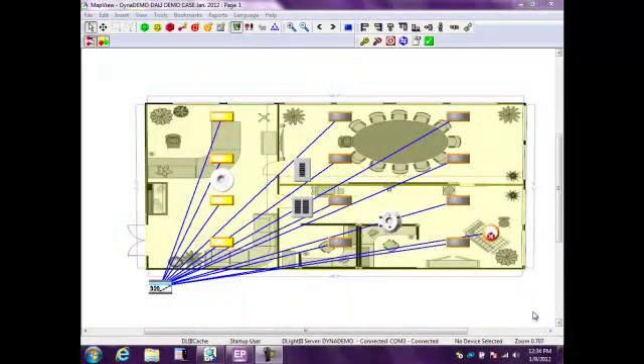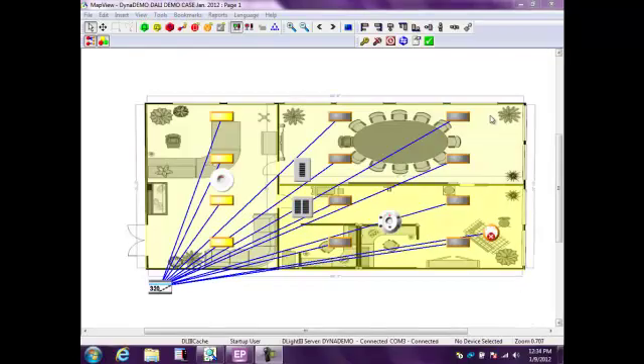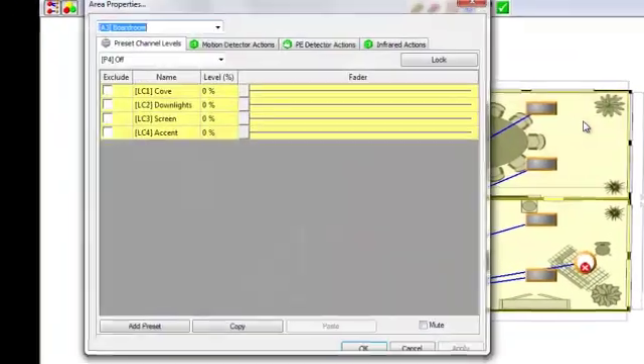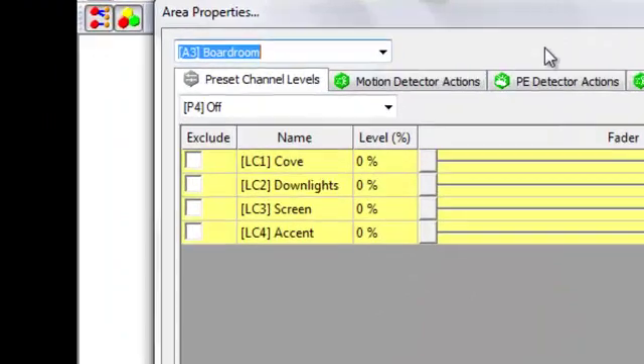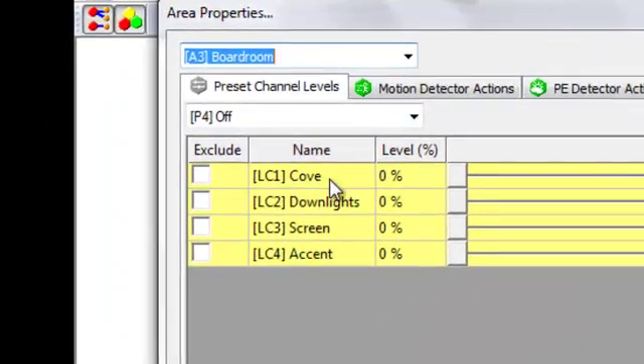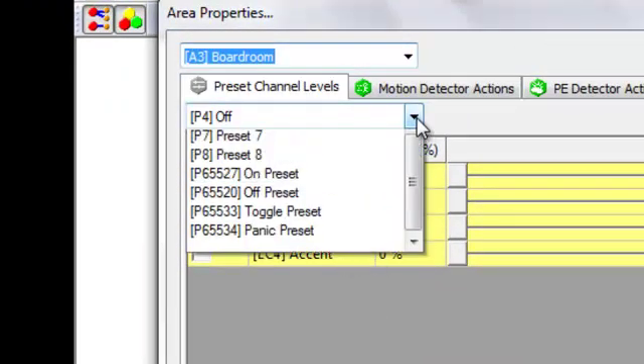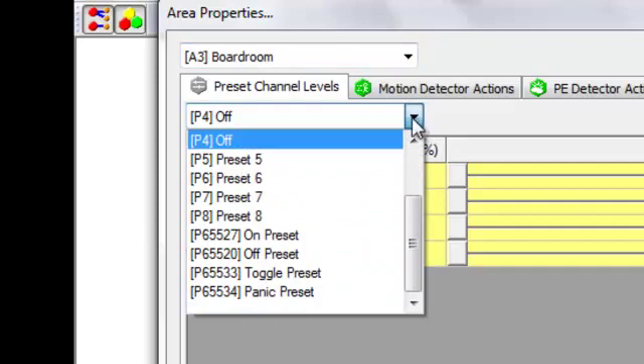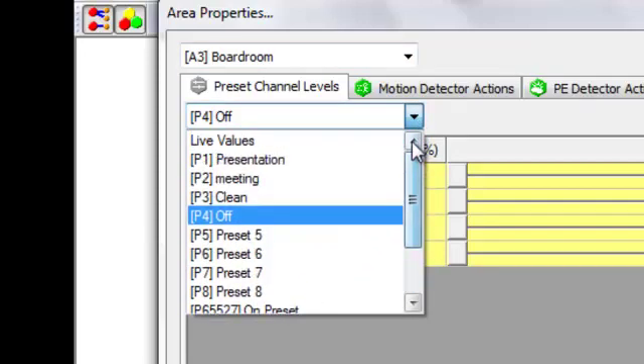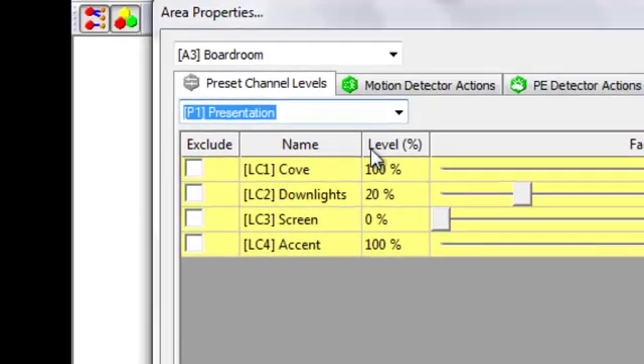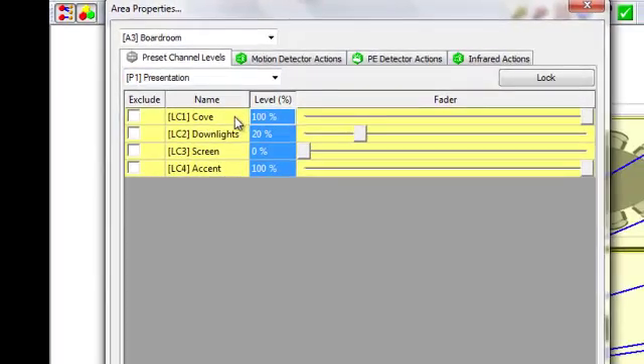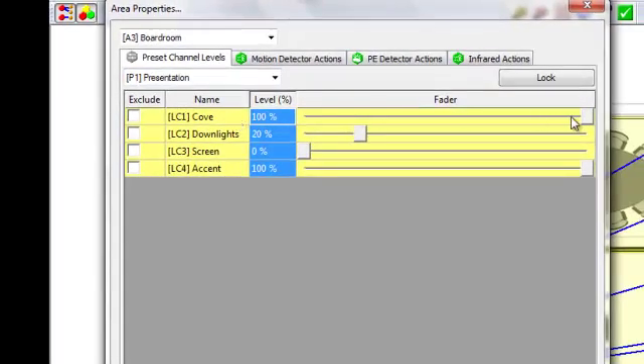We want to talk about changing a preset. We're going to go ahead and go into area 3 here, which is our boardroom, and look at what we have. In the boardroom we have a cove, down lights, screens, and accents, and we have a number of presets that we can choose from. So I go to my drop down here, and we want to look at typical uses for this boardroom. So a presentation would be a typical use. I look at my presentation and I can see my cove lights are at 100%, my down lights are at 20%, my screen lights are off, and my accents are all the way to 100%.